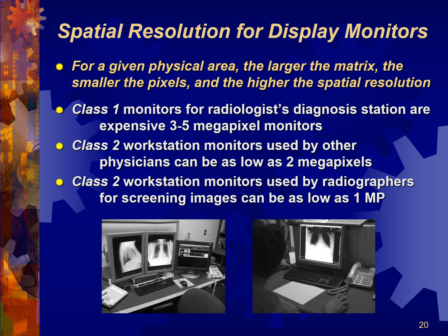Okay? So, class 2 monitors, again, as low as 2 megapixels. The actual standard is greater than 2 megapixels is a class 1 monitor. Those are the ones that are used for diagnosis. You should not be diagnosing on a class 2 monitor. Okay.